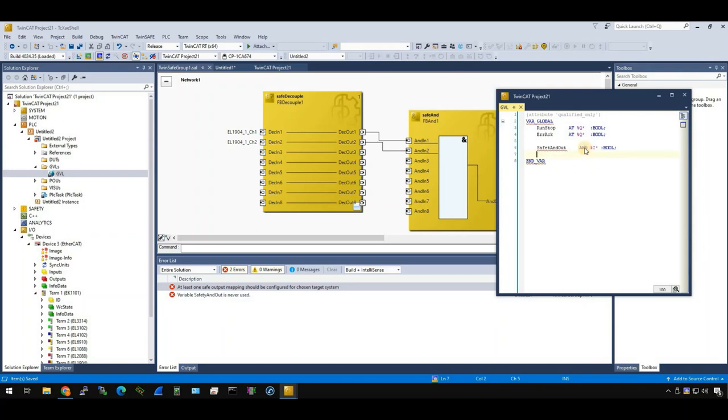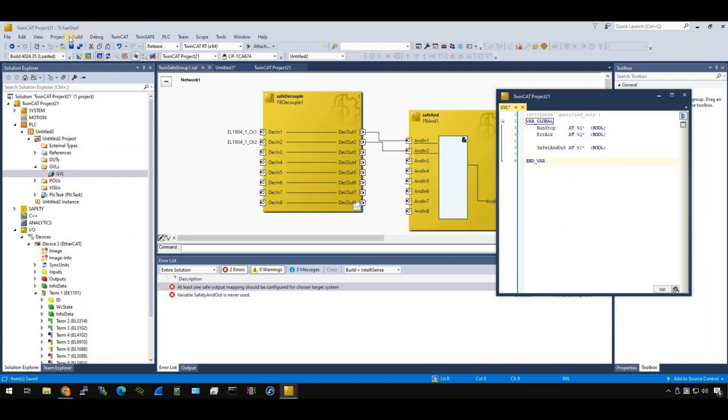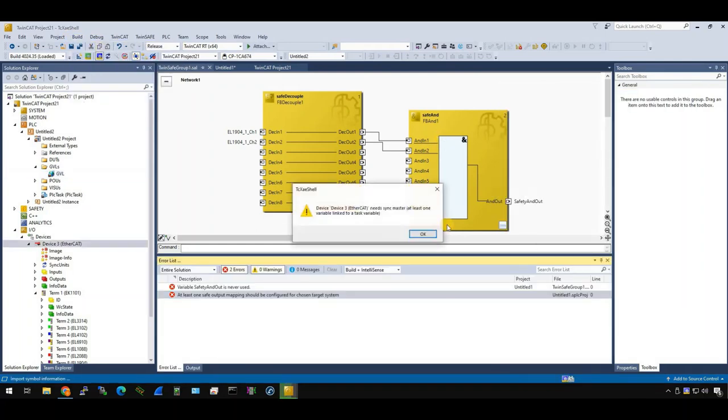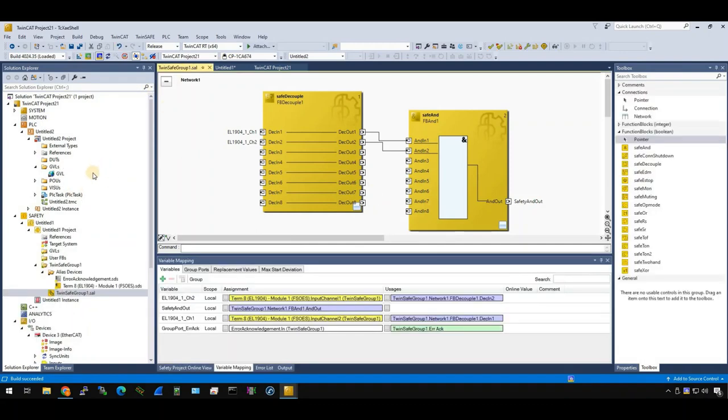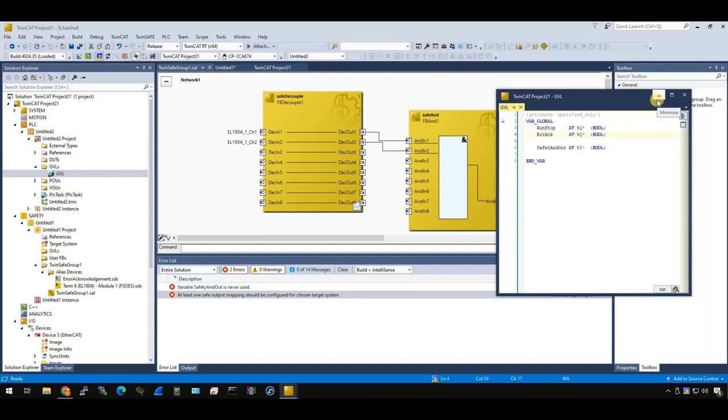Let's add, AND. This case also same because we will receive an input safety signal feedback from our safety project. So, from the safety project side, it is the output. And from our standard PLC side, it is the input. Okay, after we define it, let's go to build, build solution. Okay, just build it. Done. You need to say, something like TwinCAT, after you define the process input output, you need to build it again to use it in other side.